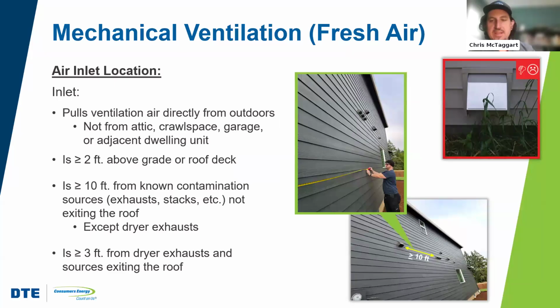Fresh air inlets, so if you're doing either supply ventilation or balanced ventilation, you have to have that inlet coming in at least 2 feet above grade or above a roof deck, and it has to pull directly from outside, not a compromised space like a crawl space or an attic. It has to be 10 feet away from known contamination sources like exhausts or combustion air, things like that. And it has to be at least 3 feet from things like dryer exhausts.